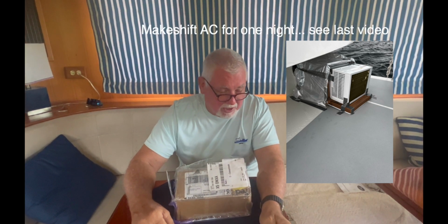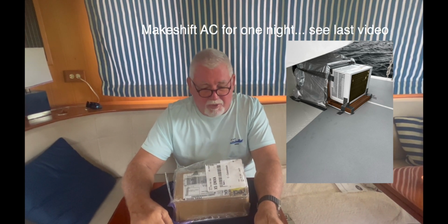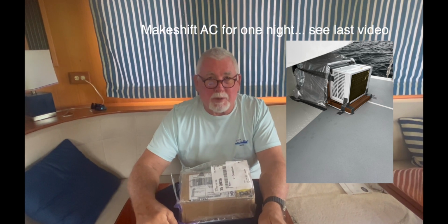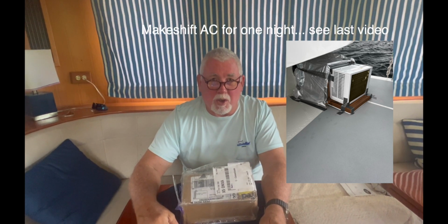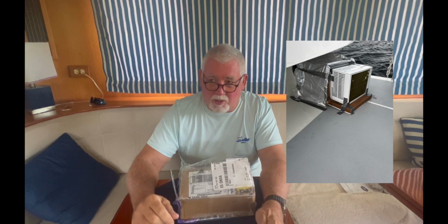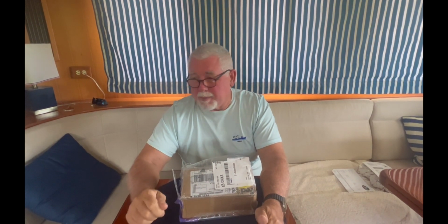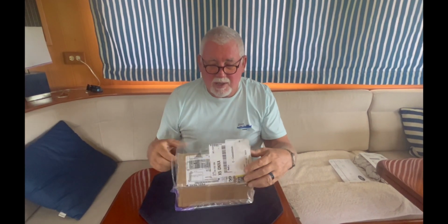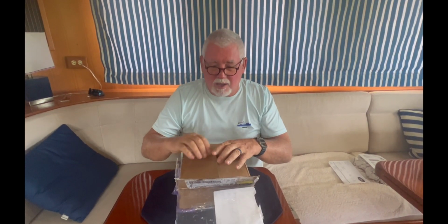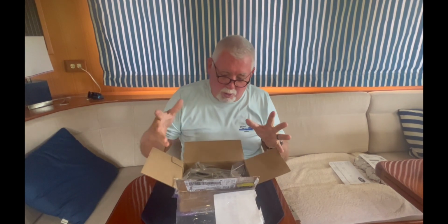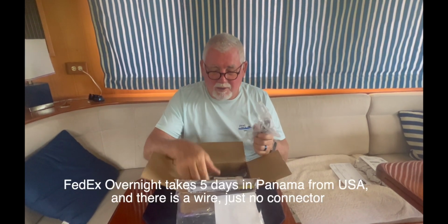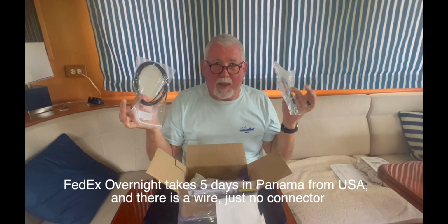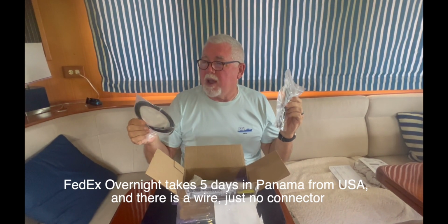Over the last week we've been having air conditioner issues, partly with the chillers. If the return water temperature sensor breaks down, the unit stops working. On the air handlers, if the temperature sensor for the water goes down, the air handler also doesn't work, but you can override it. Thanks to Yacht Tech, they overnighted, though it took 5 days, 4 of each of the temperature probes we needed.